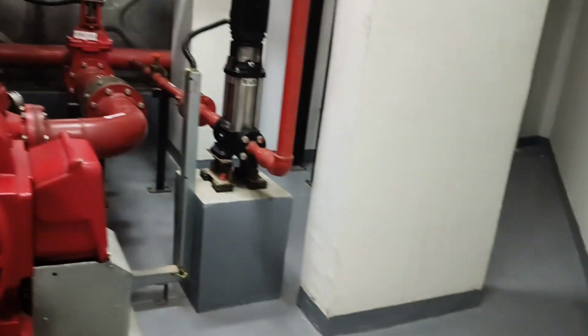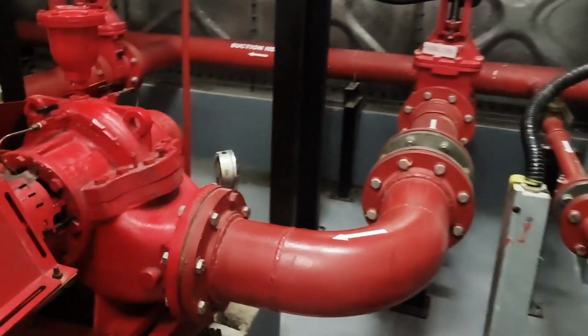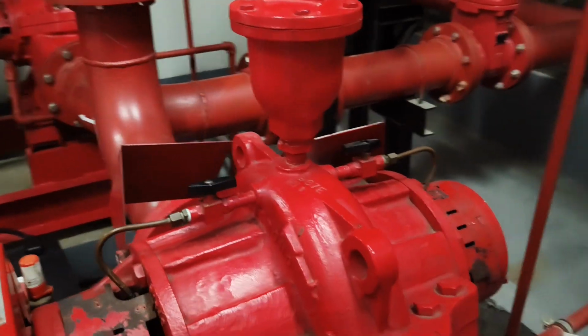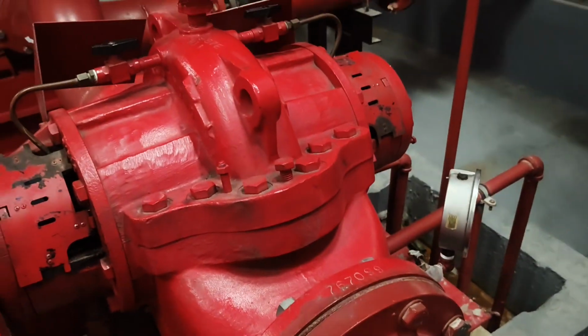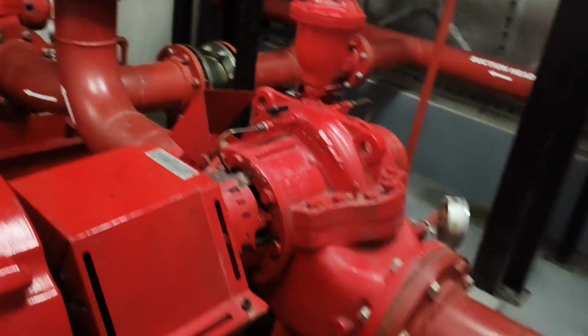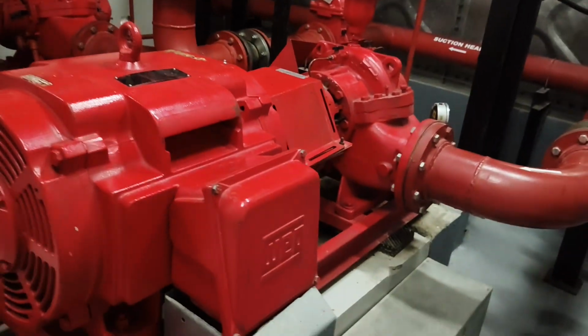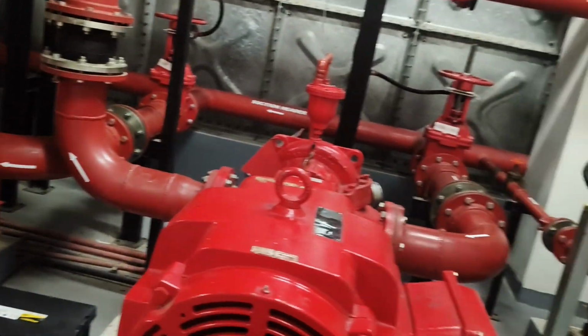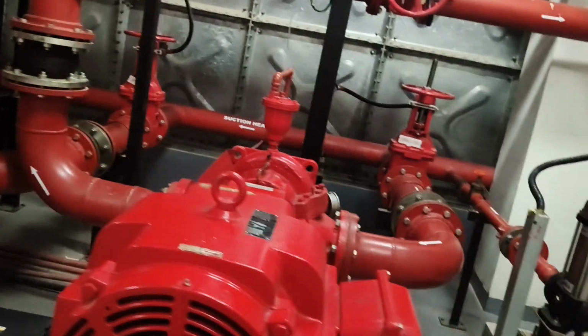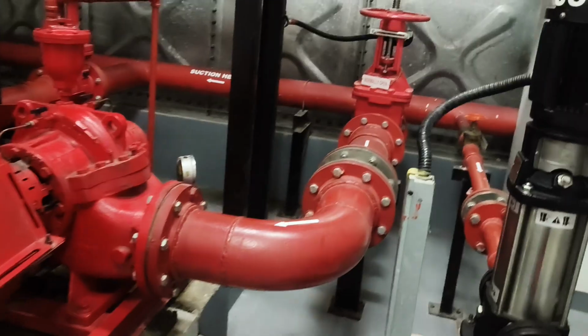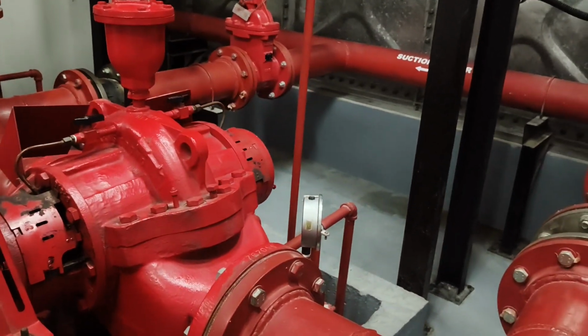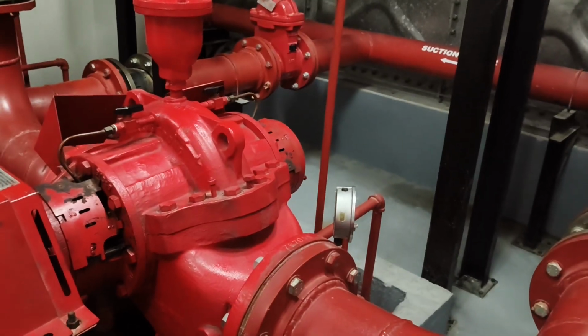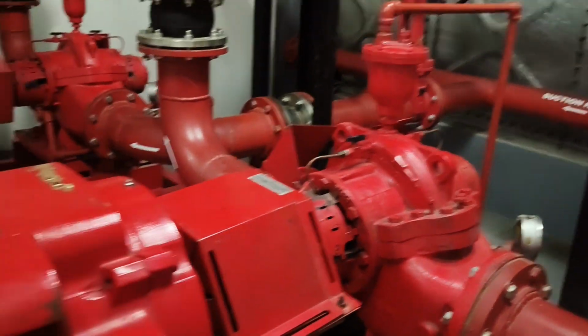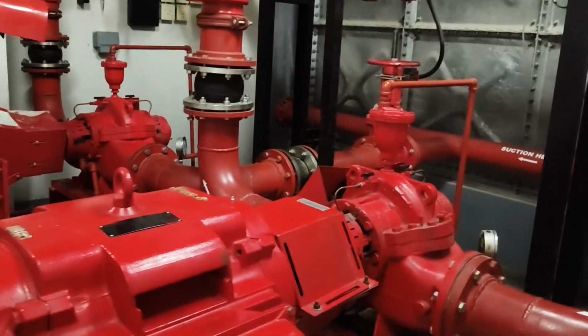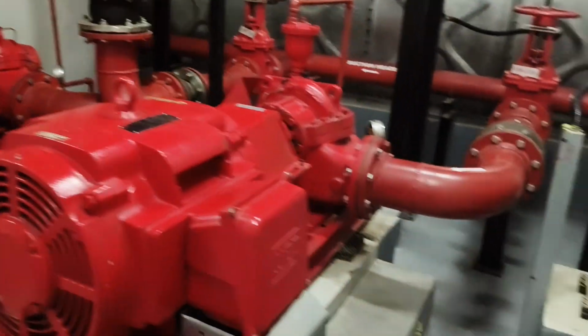And all the pumps except the jockey have a suction gauge and a discharge gauge. We call it a compound gauge, to measure the suction pressure as well. It's a requirement and it's measured. And with that, if the pressure that is coming from the suction is below -3 psi, it will be said that your flow of water into the pump is not good. So you always have to make sure that you have a good flow from your suction as well.